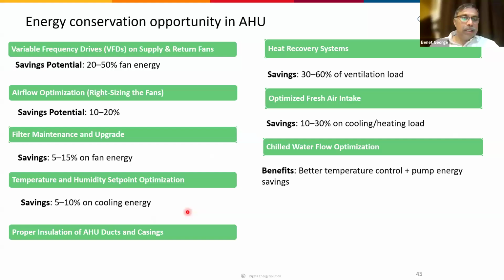So energy measures in the air handling unit: variable frequency drive. The main reason for a variable frequency drive is that the demand varies every day. The number of students who come to a college varies every day. Typically exams are there, functions are there. So there is a good opportunity for varying the airflow. Then airflow optimization, typically saying 10 to 20%, filter maintenance 5 to 15%, temperature and humidity 5% of cooling energy. Then heat recovery systems will help you recover the heat from the ventilation system.